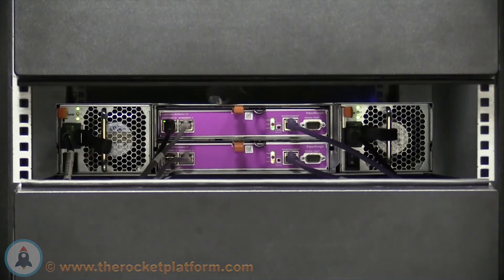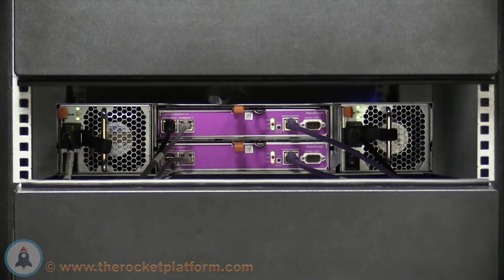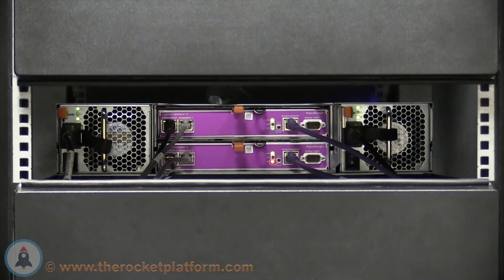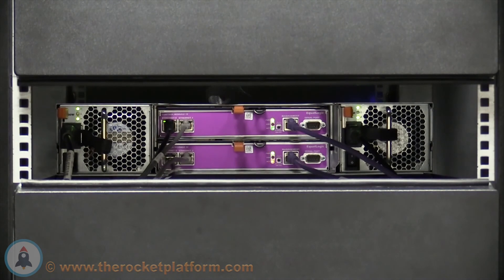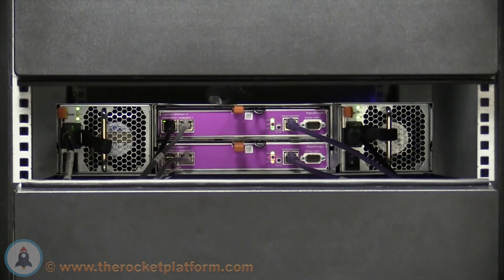In the rear of the machine, you will see the control modules. If the faulty control module is in the secondary state now, it will have a green light for the PWR and an amber light for the ACT. If the control module is in the not installed state, the controller will have a green light for the PWR and a red light for the ERR.